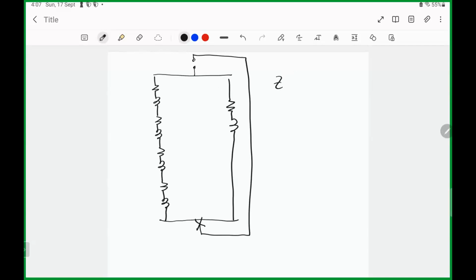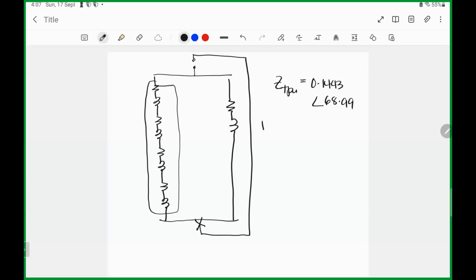So if you conduct series-parallel formula or circuit reduction, the Z_TPU now, this one is in series. Okay, this side is parallel to the per unit impedance of the motor. So Z_TPU now is 0.1443 angle 68.99. So now my I fault three phase, if I use the same formula above with respect to the impedance at the faulted point, I get now 10,002.63 amps.